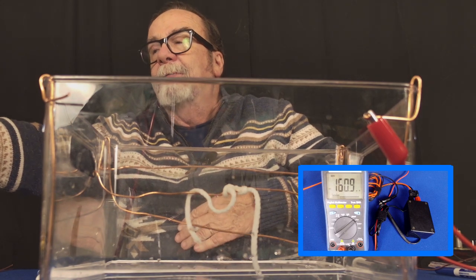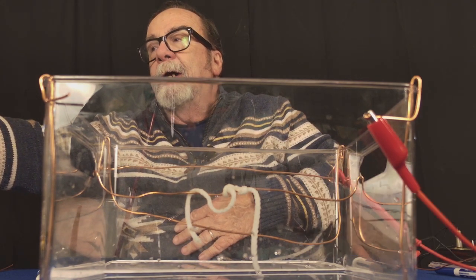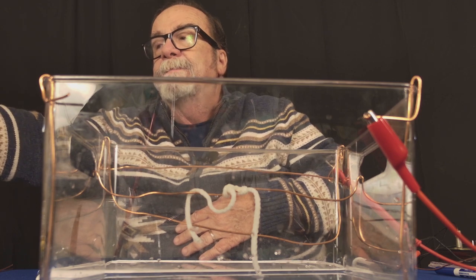Now, what I want to do is tell you a couple instances where I have found ground faults. First instance is, in both of these instances, other technicians had already been there. Couldn't find the problem. And there's nothing worse than telling a customer, I'm sorry, the ground's gone, the problem's gone, when it comes back, call me. So I go out there with this Cobb Boxx, is what I call it, power supply, and my meter, and I read, and I find that I'm reading on a module about 30 to 40 microamps going out to a PIV.